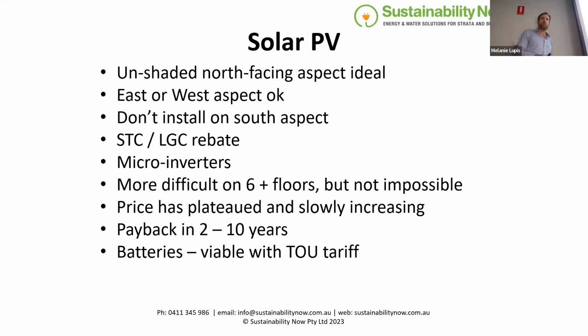That exported electricity might get you next to nothing — maybe 10 cents a kilowatt hour — whereas what you're bringing in costs you 25 cents a kilowatt hour. So if you can store that in a battery and discharge it during your peak billing period, where you might be paying 50 cents a kilowatt hour, there's a nice margin of about 40 cents a kilowatt hour that can help pay the battery back in less than its design life. So it's definitely a prospect for some buildings, if you can fit enough solar up there that it would otherwise export to the grid.